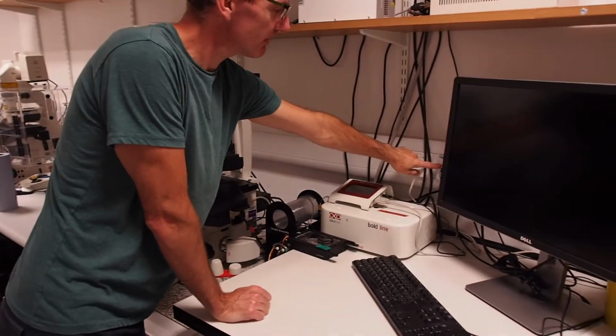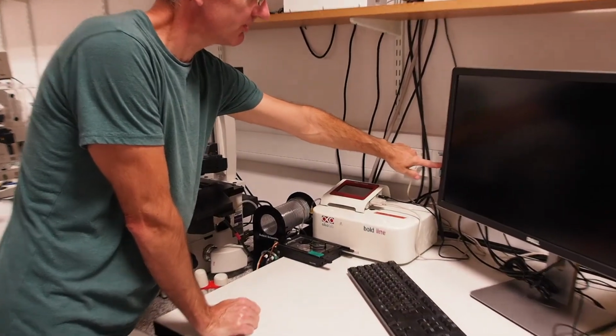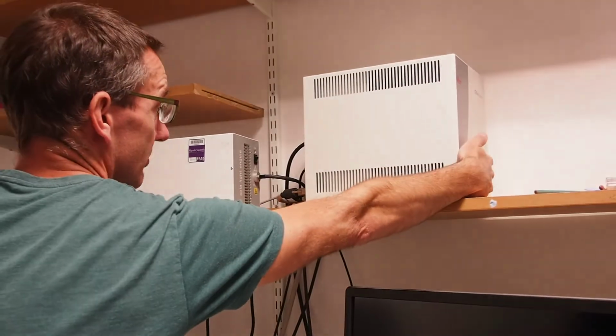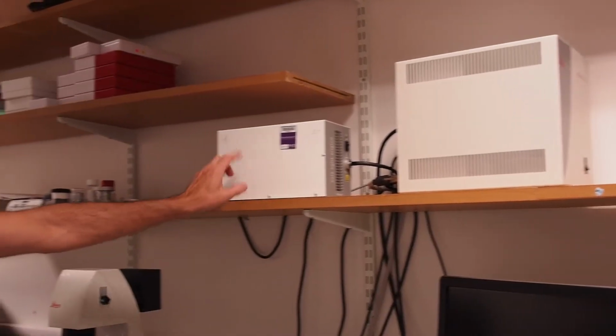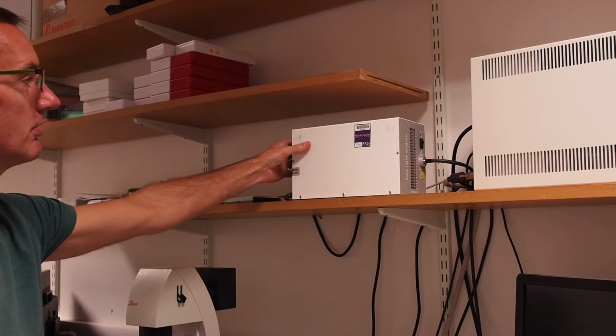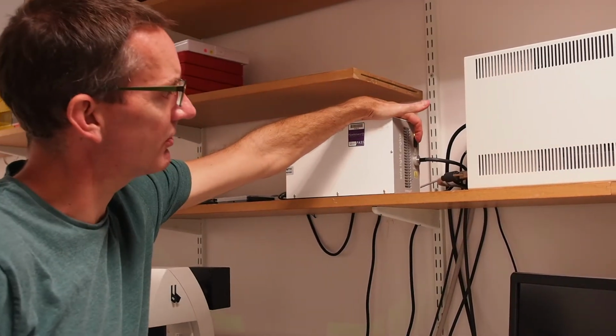Switch on the power for the Flash 4 fluorescence camera at the wall, then turn on the microscope power with the CTR box on the shelf. Next, turn on the fluorescence LEDs using the switches for the power first, label number 1, and then the shutter, label number 2.